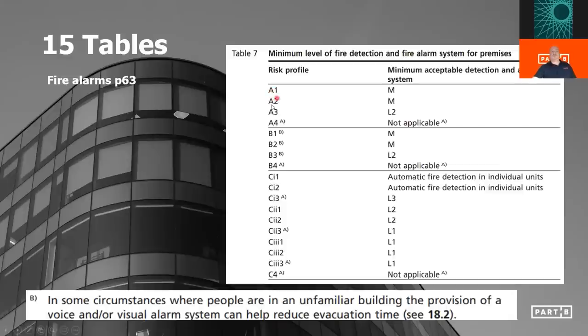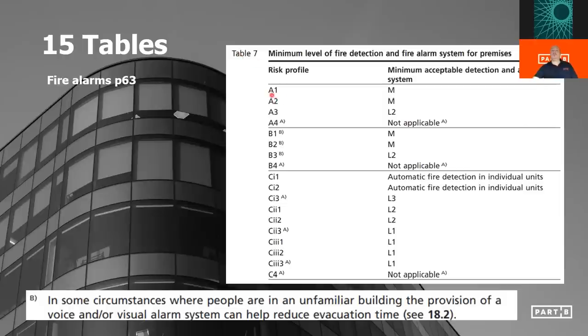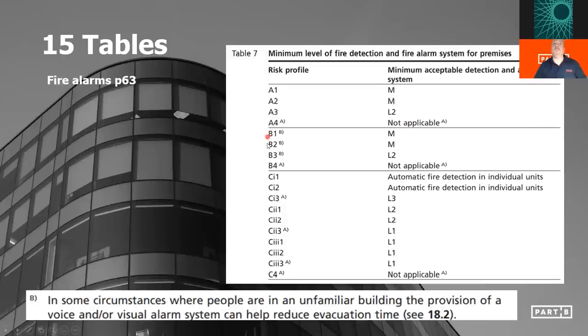BS9999 does not consider things like water mist systems or anything else like that. They may have a protective effect on people within the building, but BS9999 doesn't recognize water mist systems just yet. Looking at the minimum package: everything comes from the risk profile, and we apply the tables. Table 7 within BS9999 tells you the minimum level of fire detection and fire alarm system required for premises. For an A1 building, the minimum acceptable detection and alarm system is Category M — just a manual call point system, with red manual call boxes at exits and every 45 or 30 metres. A2 is also M. B1 and B2 are also M. Once we get to a fast fire growth rate, we want to pick it up quicker, so we want an L2 system in there.